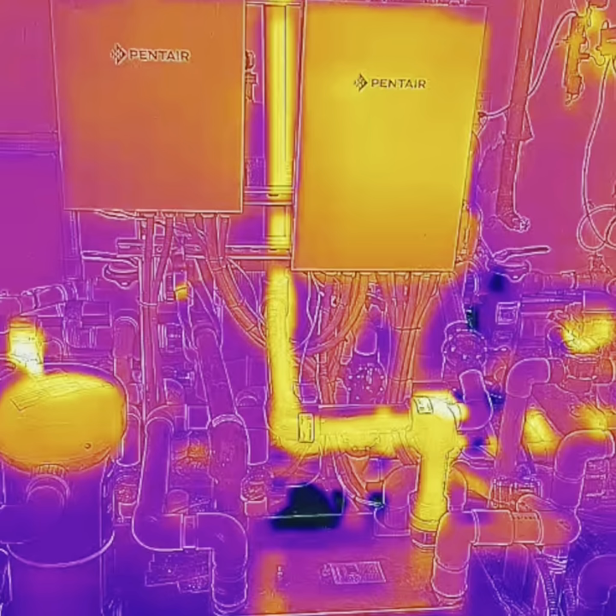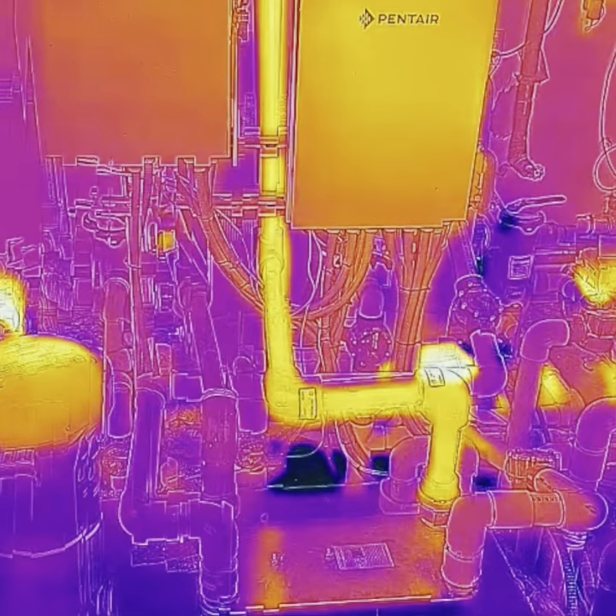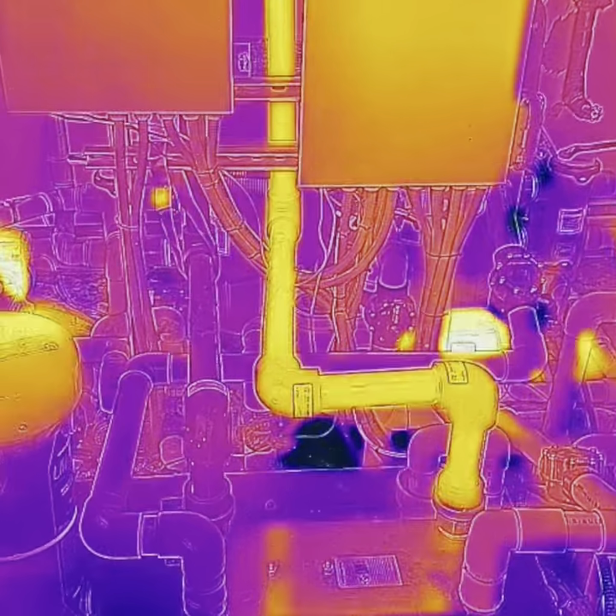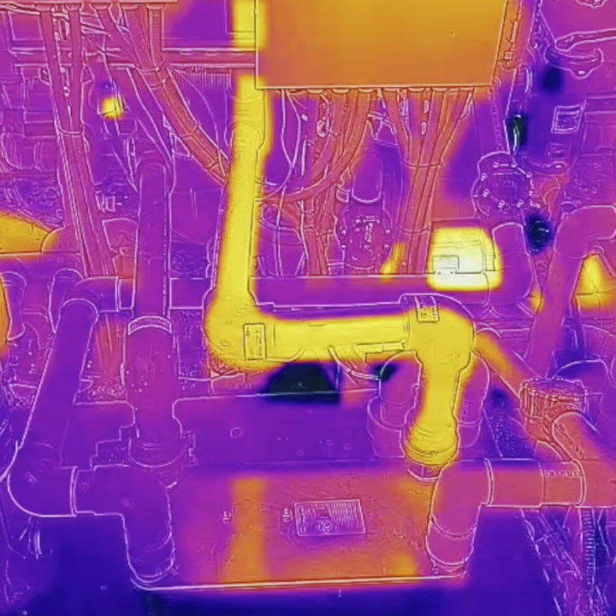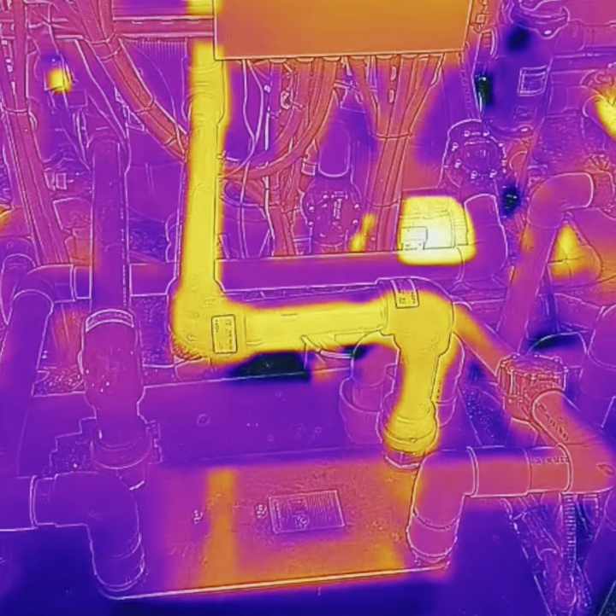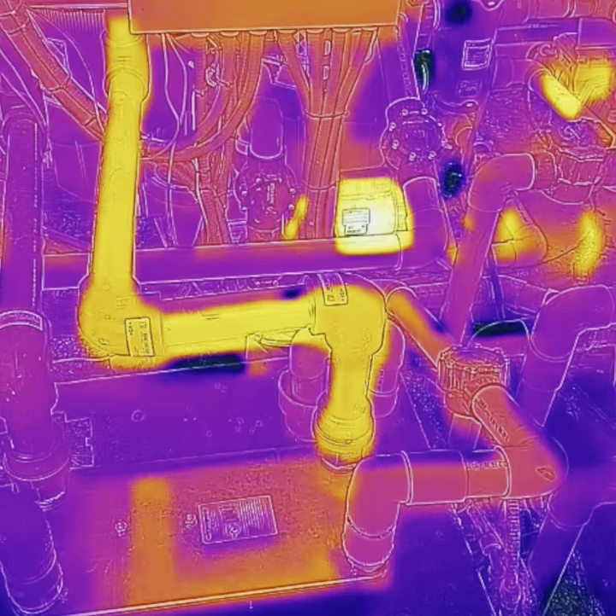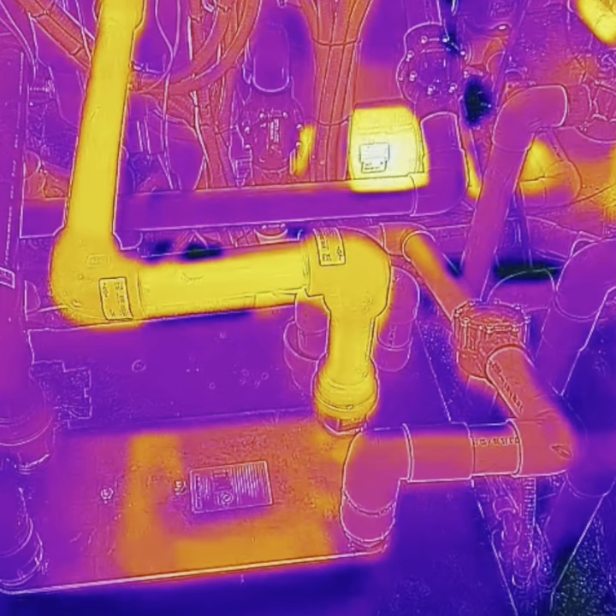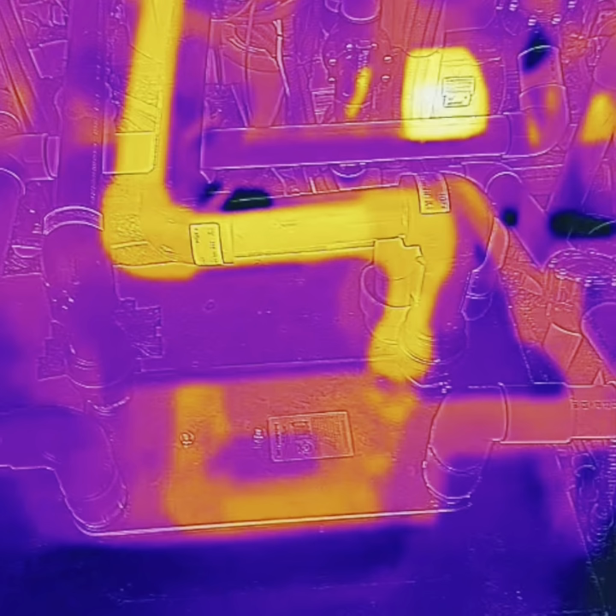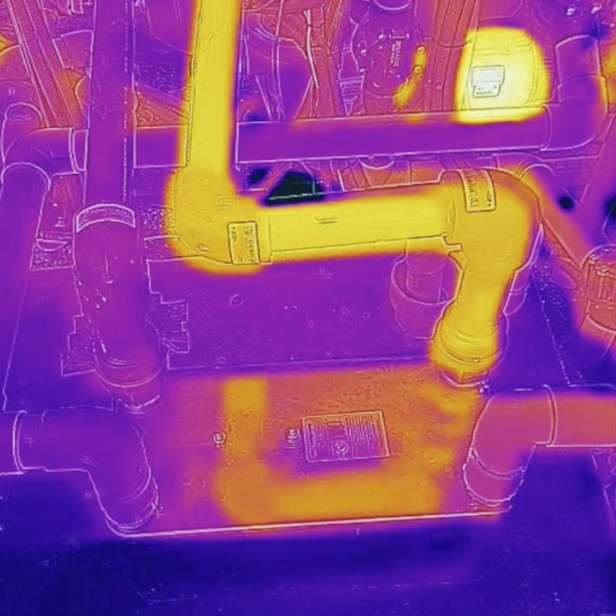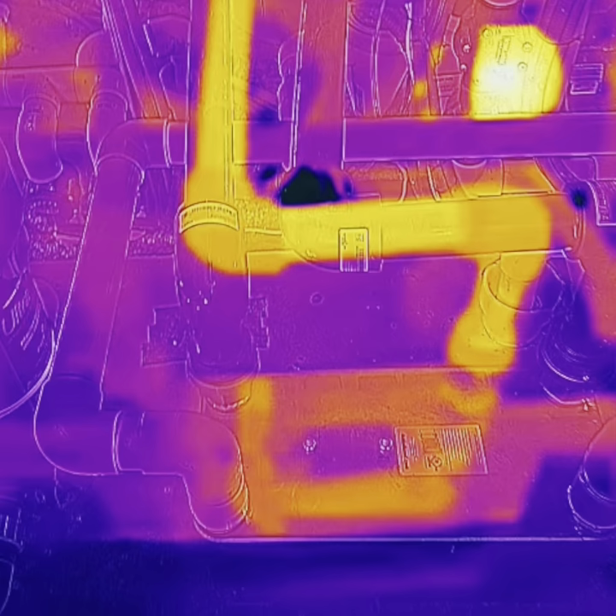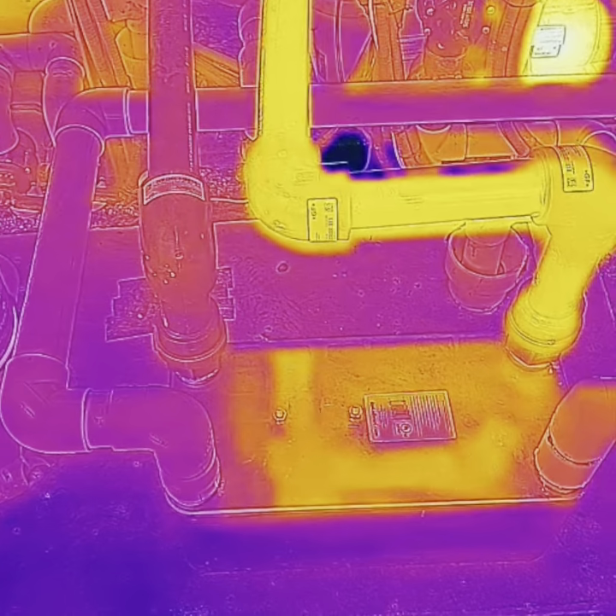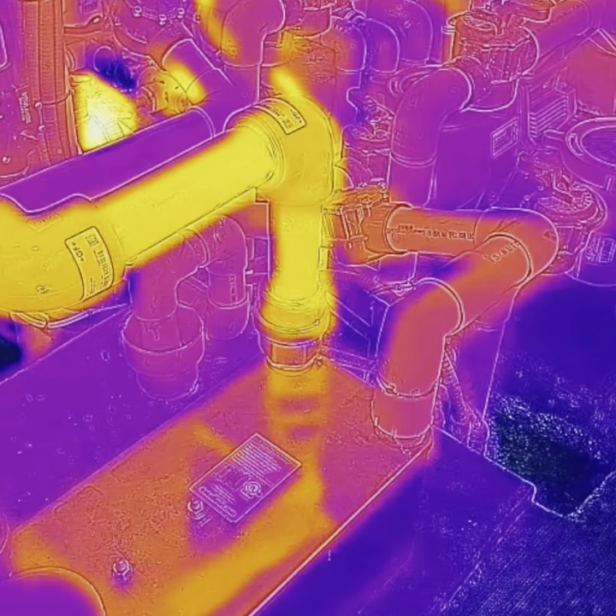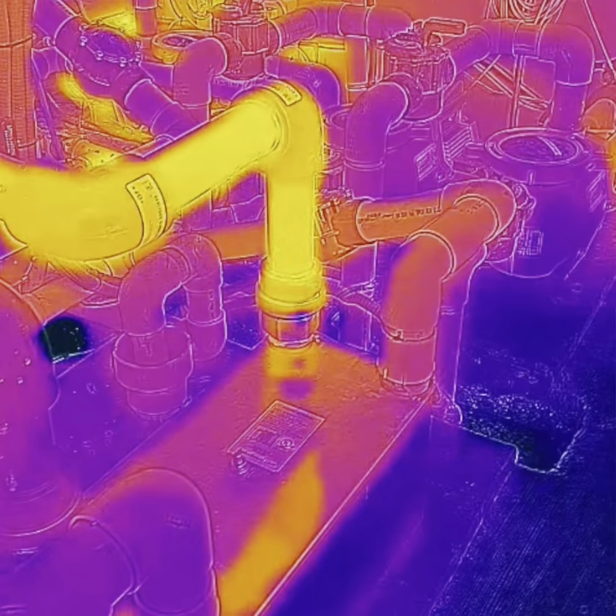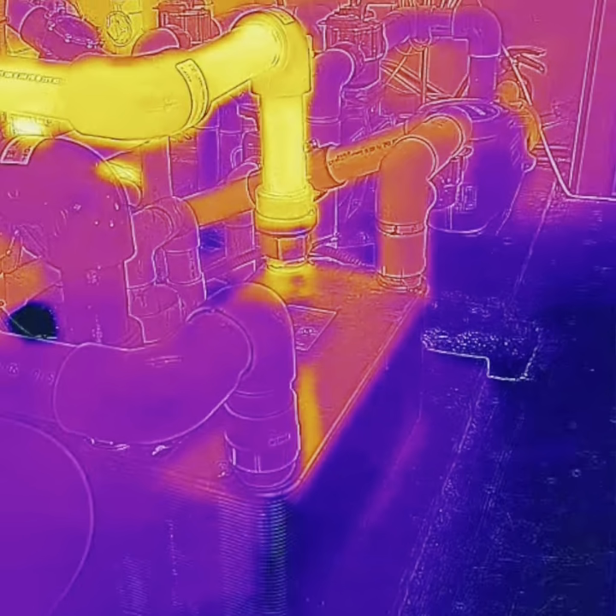Here is the heat exchanger, and you can see those same pipes coming in. The ones in the front run in opposite flow—the one on the right is going to the pool, so you can see it's warmer than the one on the left, but not quite as warm as that other water. That's due to velocity differences, how much water is moving through these, which is why we won't have an exact in and out temp. But as you can see, there's definitely warmer water going back to the pool than coming into that heat exchanger, and that's the goal—that's what we're here for.